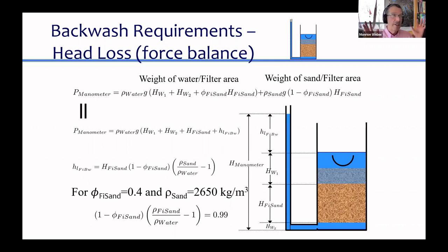Here's one very simple practical result. Our stacked rapid sand filters are very carefully designed, and they're designed for using silica sand. If you, as a very clever engineer, said, I think it'd be more fun to use garnet in those crazy stacked rapid sand filters, and you took out the silica sand and put garnet in it, and then you tried to backwash it, it would be a complete fail. The filter hydraulics aren't capable of delivering enough pressure to backwash garnet. Anybody want to ask a question?